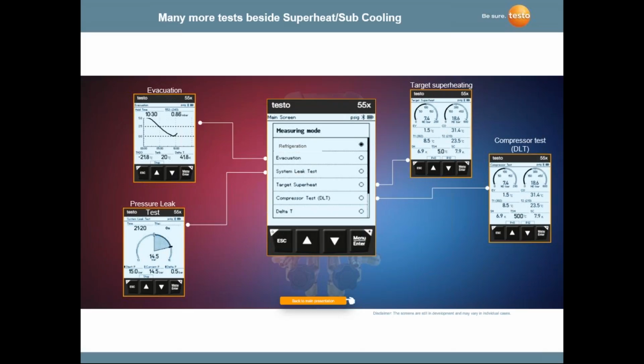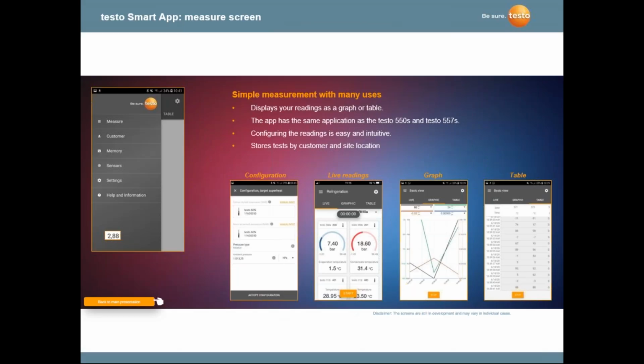Compressor test, you can actually use up to 3 temperature sensors simultaneously, one on the discharge line of the compressor, and you can still do the superheat subcooling readings. And then you've got your typical delta T, so you can measure across coils, you can measure across filters to see any temperature differences over a distance. The app is, again, very easy to use. It's a Testo Smart app. It's free. The big thing that's new on our app is that we now have the capability of storing readings by customer. Details of the customer information can be put into the app, as well as the site location, which would be the equipment, maybe the equipment serial number, the type of equipment, things of that nature.